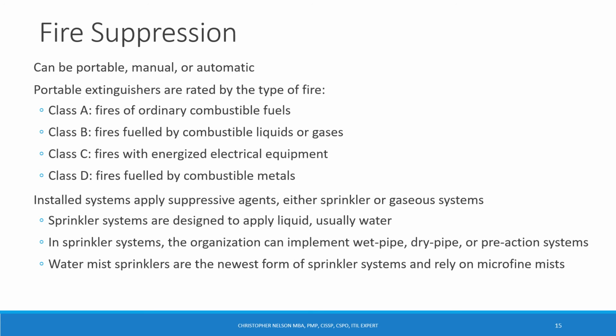For fire suppression, this can be portable, manual, or automatic. Portable extinguishers are rated by the type of fire. Class A, fires of ordinary combustible fuels. Class B, fires fueled by combustible liquids or gases. Class C, fires with energized electrical equipment. And Class D, fires fueled by combustible metals.